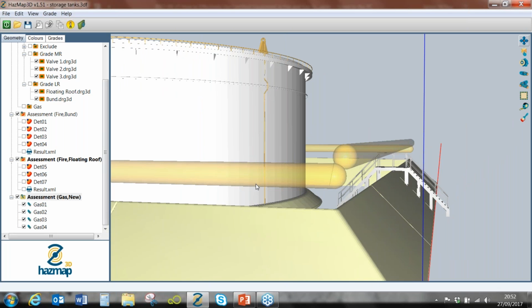Now, people may walk back and forth and cross the beam, but we're not too concerned about that because with open path gas detectors, you can install a time delay, which means that something would have to block the beam for a certain specified period of time, for example, 10 seconds. So you would have to have someone standing at the top there for 10 seconds, and then the detectors fundamentally fail safe. It will provide a beam block fault to the people in the control room to essentially send them to go and investigate. Or the person will move on and the beam block will clear.